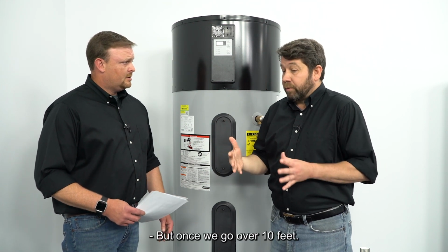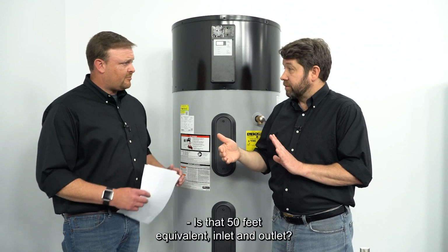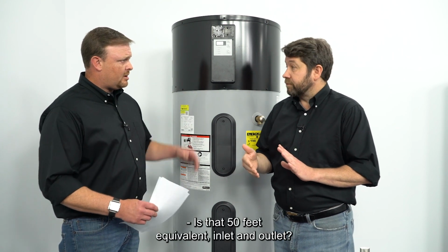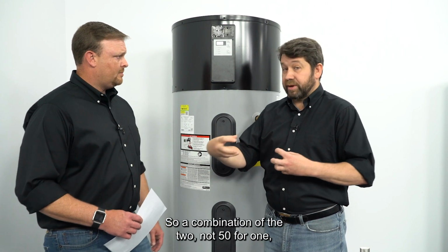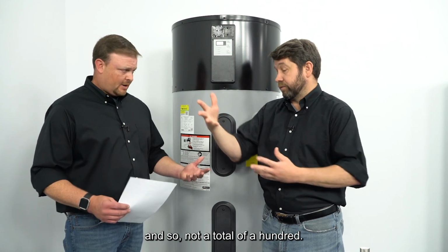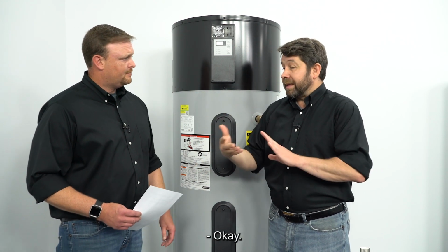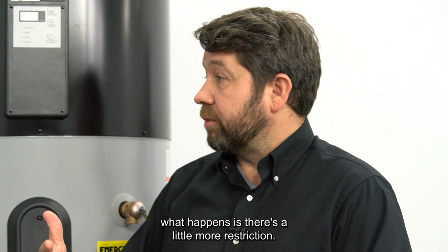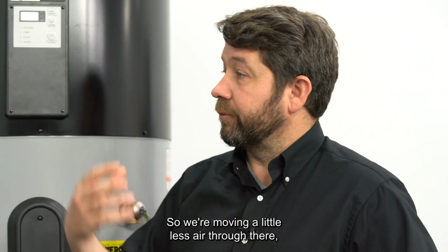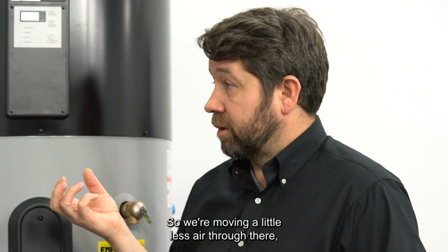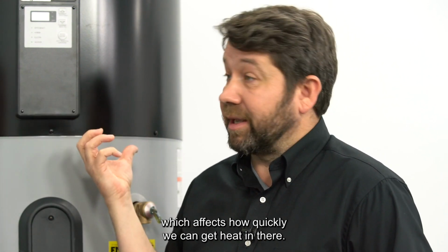Okay. But once we go over 10 feet, is that 50 feet equivalent, inlet and outlet? So that's inlet and outlet combined, a combination of the two, not 50 for one, so a total of 100. Okay. If we go over 10 total feet, what happens is there's a little more restriction, so we're moving a little less air through there, which affects how quickly we can get heat in there.